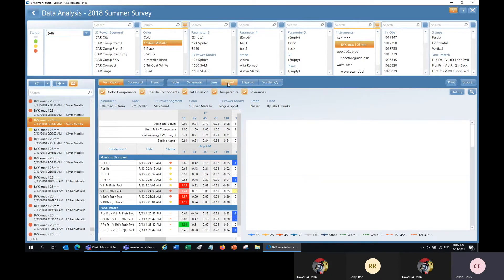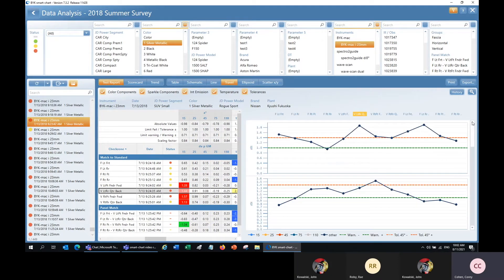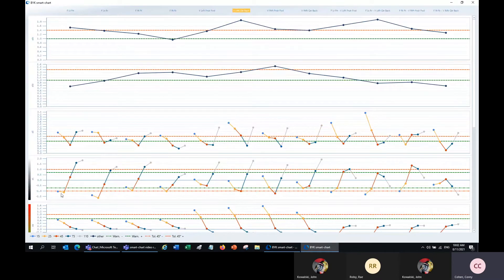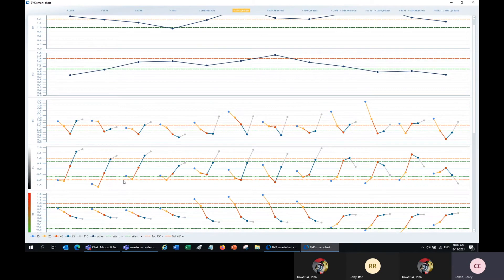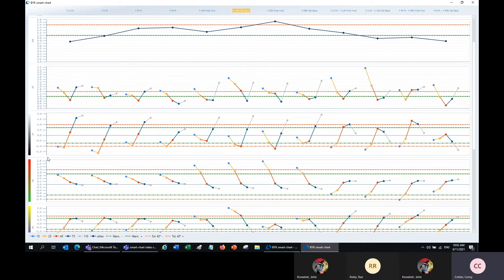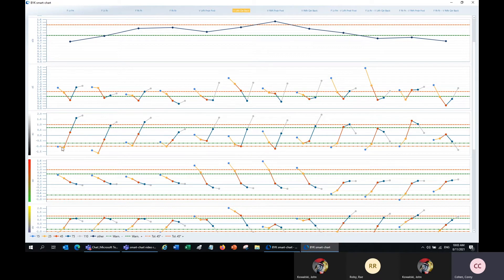If I click the travel tab at the top, I can view graphs that show the change from angle to angle for each measurement. Each different color is a different angle, so I can see how, for example, the L value is changing for a single check zone. The important thing here is not that the value is changing — it's that the travel is the same across each check zone. You want to make sure that each check zone has the same general shape for these travel graphs.